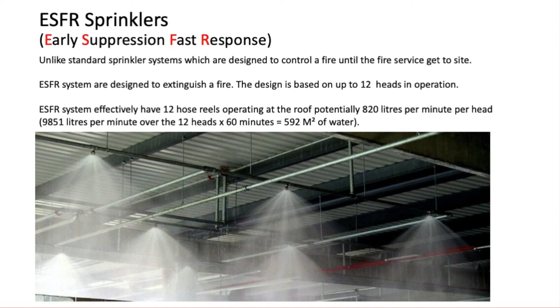So the way I like to picture it is you've got 12 hose reels at your roof operating, potentially 820 litres per head. So you could have 9,851 litres per minute, okay, over 12 heads. So again, 592 metres cube of water on your floor. Now that might be more than that, might be less, depends what heads you pick. Some of these heads operate at 3.5 bar. Okay. So it works different. So it's the number of heads in operation. So if you just imagine 12 hose reels shooting water straight down, and that extinguishes the fire.